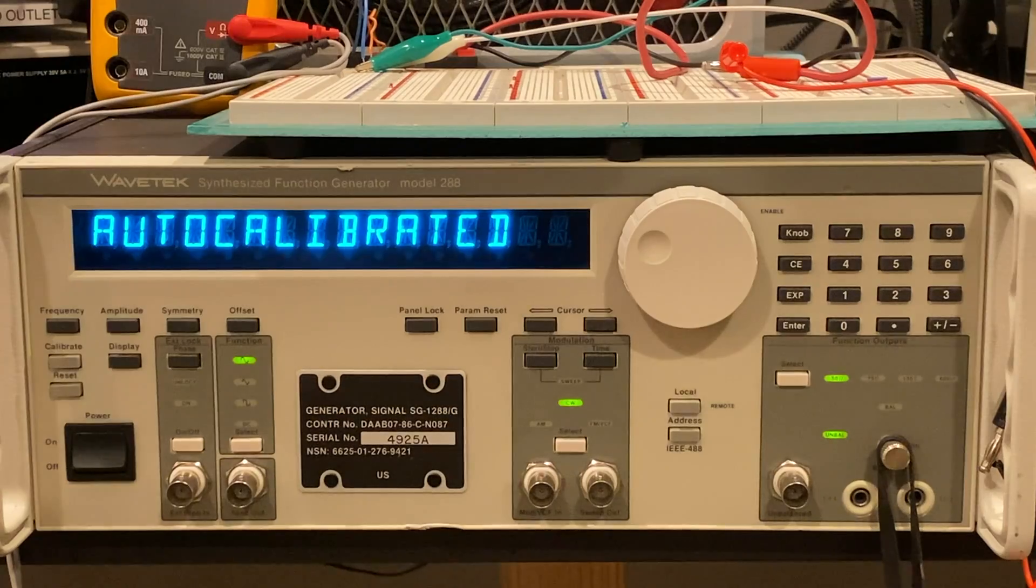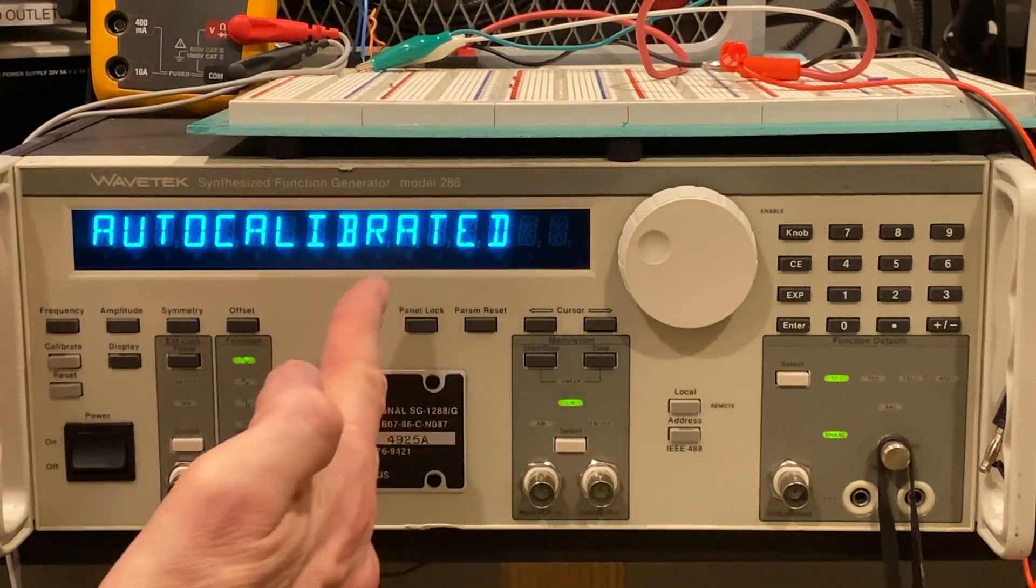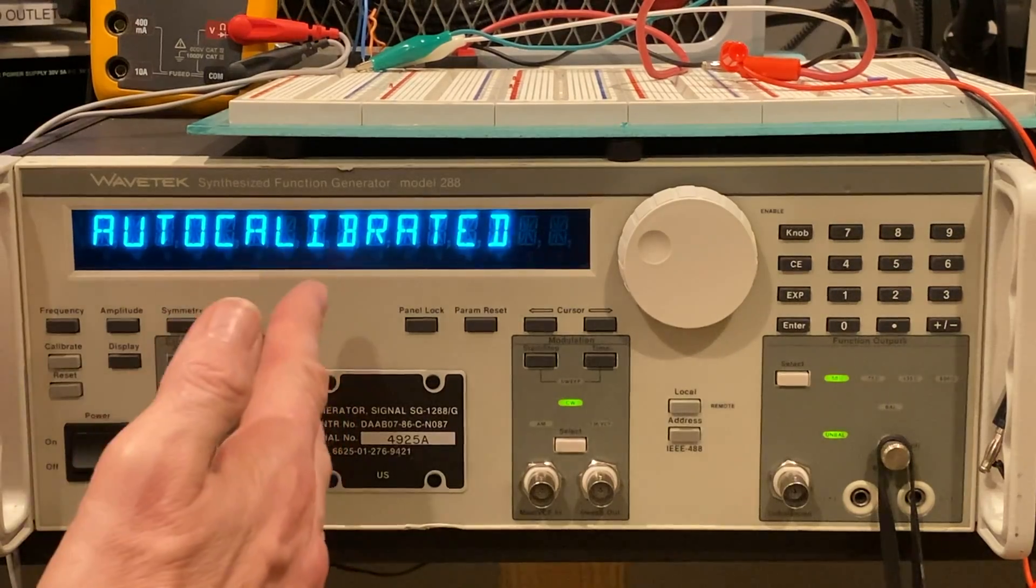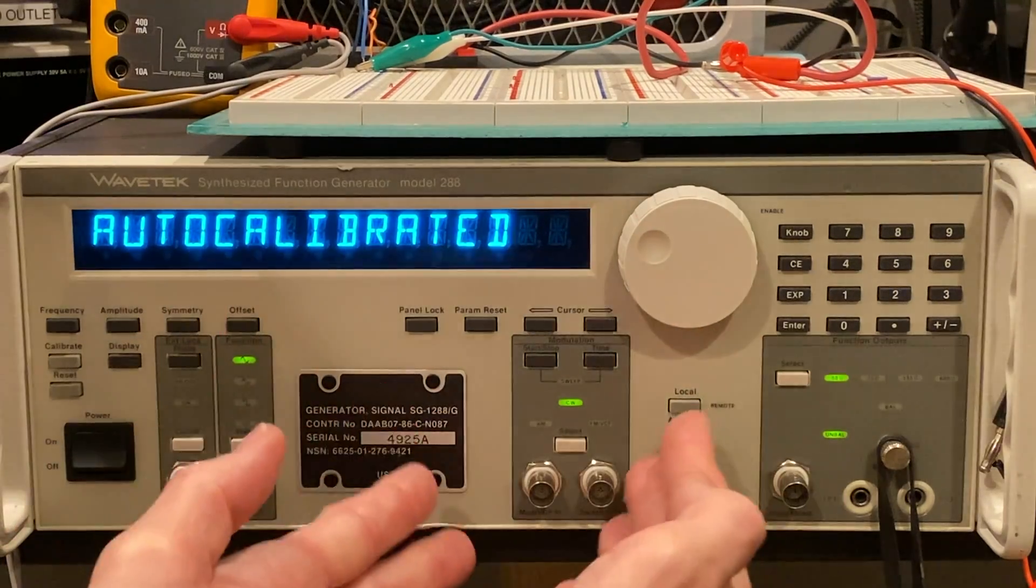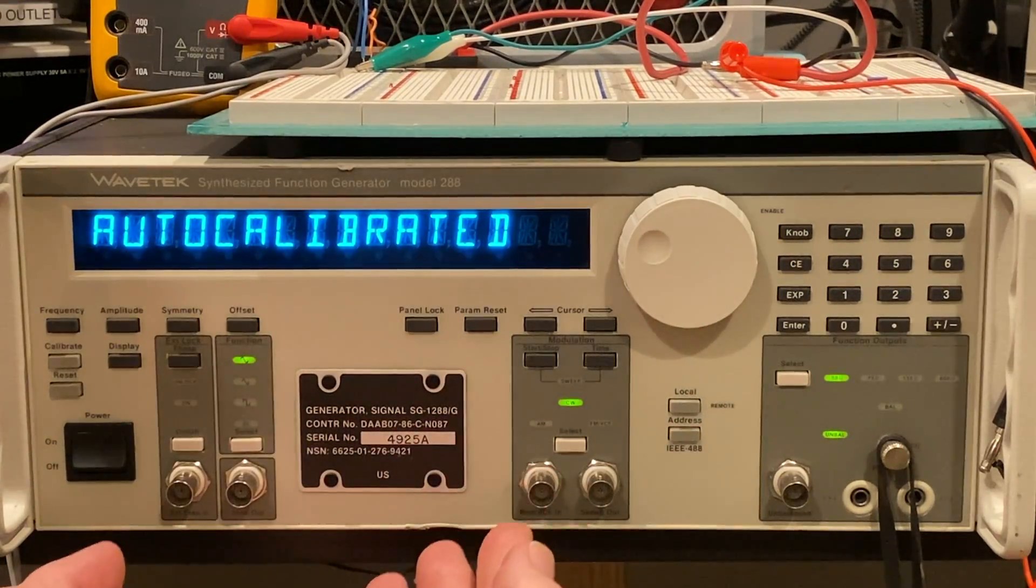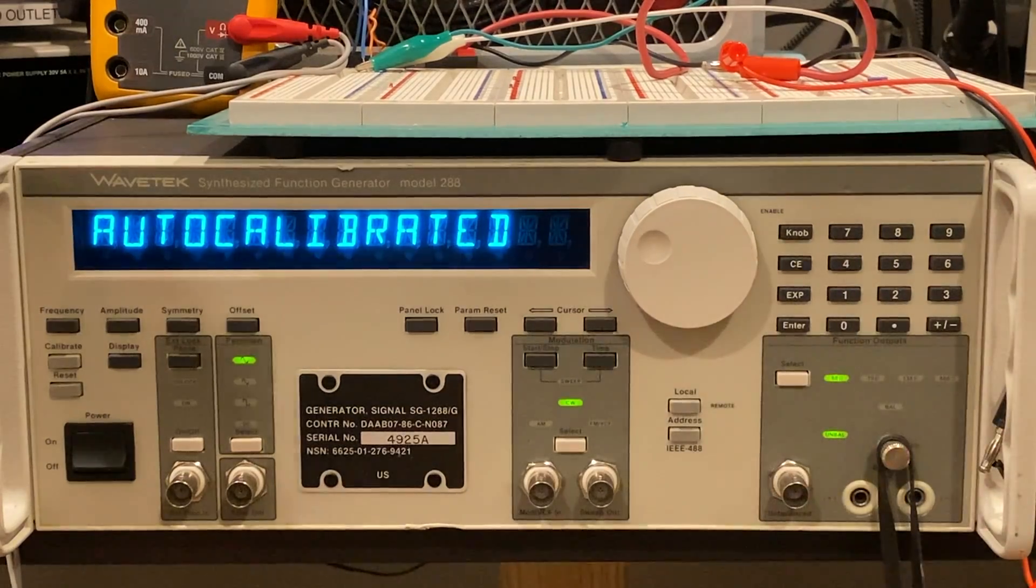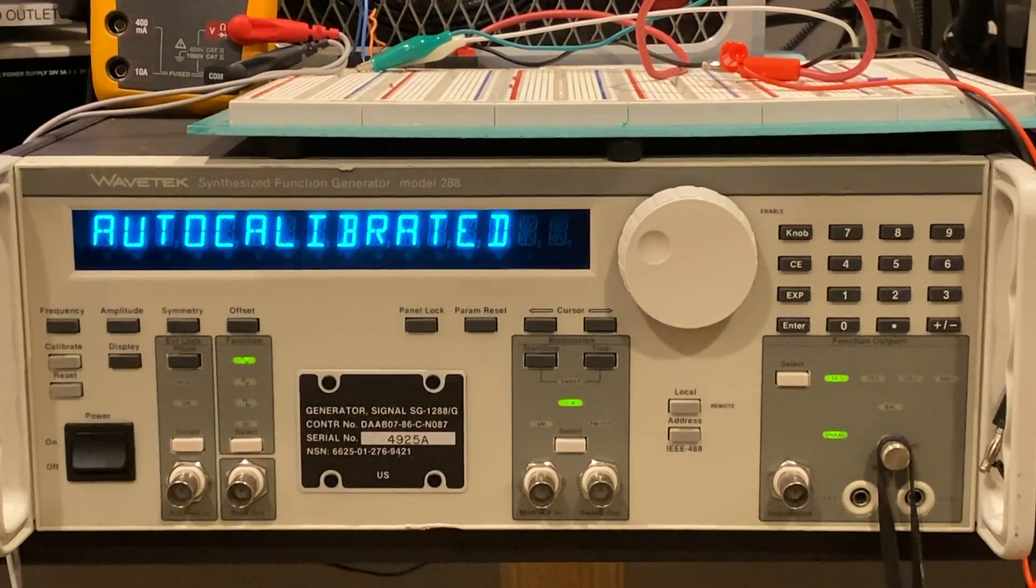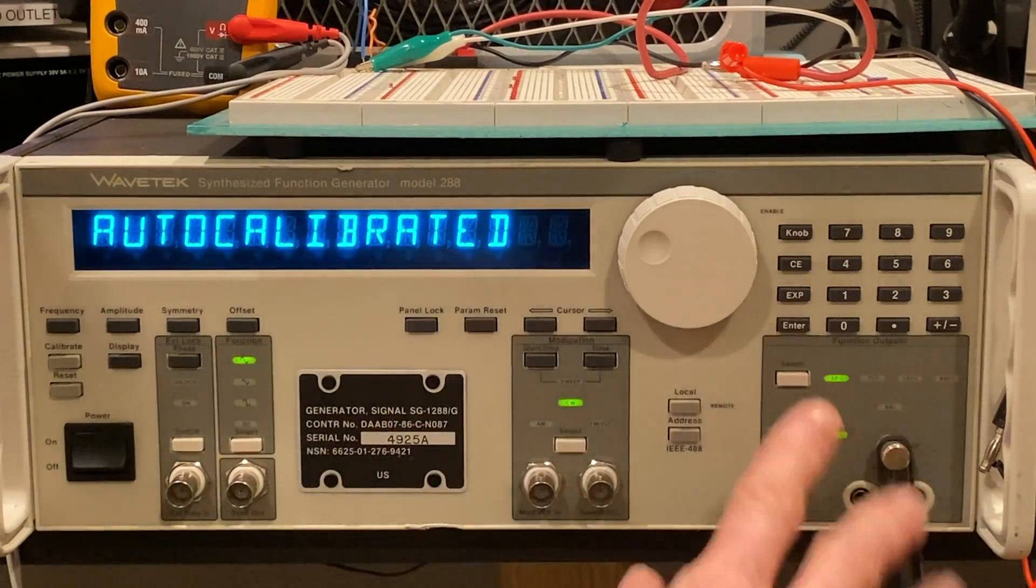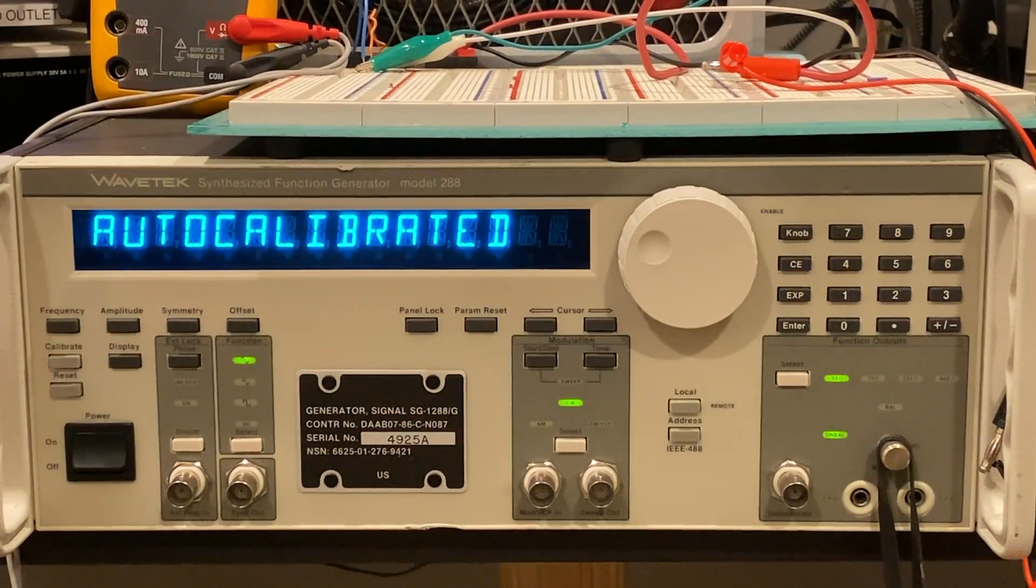So this particular unit is synthesized, meaning that it has a function generator aspect here, very basic, but it has more of a signal generator aspect here in the center with this particular setup and capability. This here is just a control panel. We can see that the unit's been on for 20 minutes. It has auto calibrated and we'll talk about the features briefly and then we'll look at the signals on the oscilloscope.